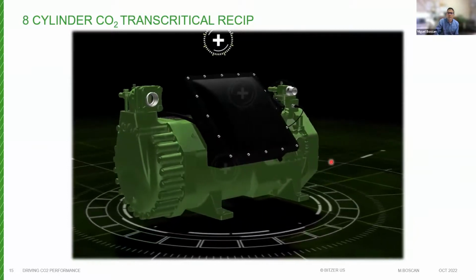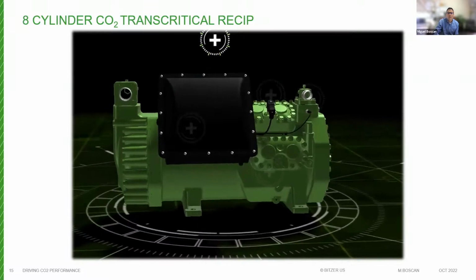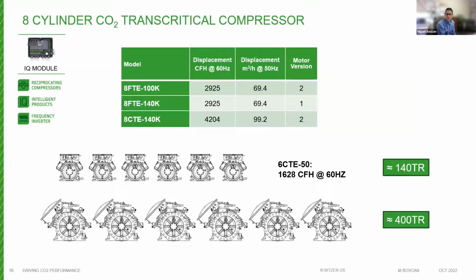This compressor is quite a bit larger than our current offering. A quick comparison with our largest transcritical model, which is a 6 CTE compressor: the FTE displacement would be about 80% larger than the CTE, and the displacement of the largest 8-cylinder compressor is more than 2.5 times the displacement of our current CTE compressor. Most likely these compressors are not going to be used in your traditional supermarket, but they're a great option for any of your cold storage facility needs, really reducing the number of compressors if you are going to a CO2 option for cold storage or larger applications.